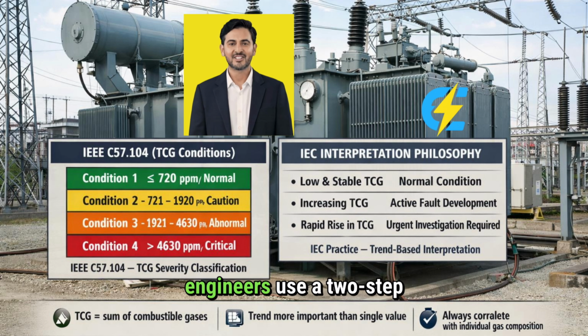This is why senior engineers use a two-step approach: TCG for classification and individual gases for diagnosis. TCG tells you when to act, while other gases tell you how to act. Never panic over TCG alone, but never ignore it either. The trend of TCG values is often more important than a single absolute value. A rapidly increasing TCG, even if still in condition 2, might be more concerning than a stable high TCG that's been constant for months. Understanding the limitations of TCG is equally important.